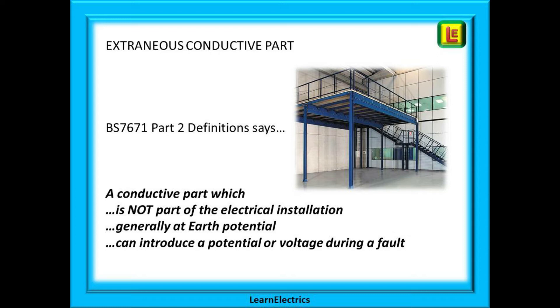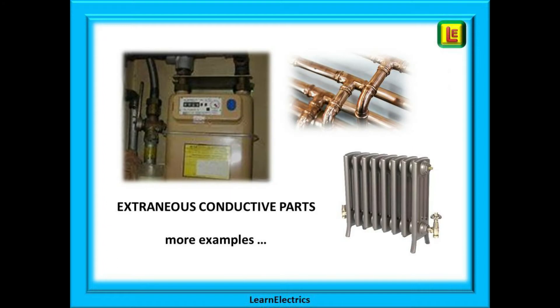Extraneous conductive parts are defined as those things that are not part of the electrical installation. They are generally at earth potential because of how they are positioned or constructed, and they can contribute to voltage differences during electrical faults in other parts of the installation. Because of their earthy connection — for example, in the ground — they can act as a zero point for electric shocks.